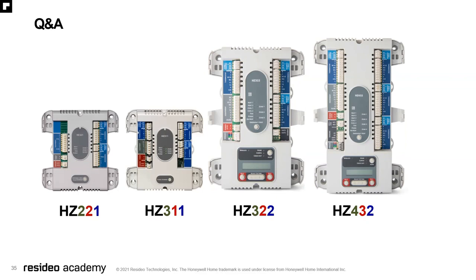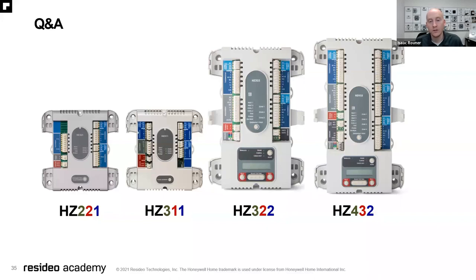The second question: how many wireless thermostats does the wireless adapter allow? The wireless adapter makes the zone panel wireless, so it really comes down to how many zones the panel can control. For example, the HZ322 gives you up to three wireless zones; the HZ432 gives you up to four wireless zones. You only use one wireless adapter per zone panel, and that allows you to make the whole panel wireless or select specific zones to be wireless.